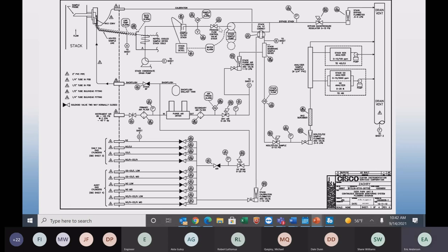it's the pump. I mean, it could be the Teflon tubing going to the pump. That Teflon tubing is very soft. If it rubs on itself or any metal tubing or piece, you'll see some white powder there, and that's the Teflon falling apart, and it'll actually rub a hole in the tubing there. So tubing here, and then of course this is on the pressure side. But anyway, here's what we're talking about.